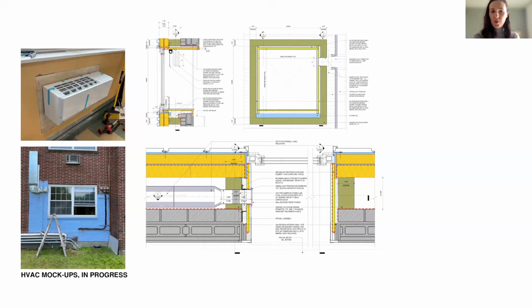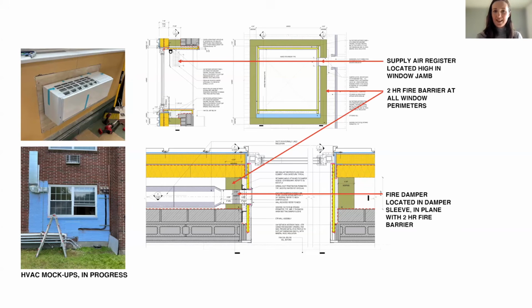And so we're doing that with a product called Side Rise, which lives its regular life in a curtain wall fire stopping application. So through a series of EJs and code evaluations, we've gotten the green light to use it in this capacity. You'll see we've got our fresh air register located high in the window jamb. And then we've got a fire damper, as well as having to coordinate that with window shades and whatnot. And then, of course, our air barrier connection. There's a mock-up of just this part too, of how do we actually do this connection? How do we successfully execute that with all these parts and pieces? And how do we do it in a timely fashion? Because we've only got 1 day to do it per dwelling unit.